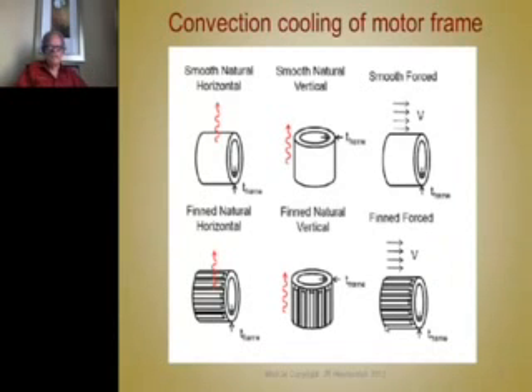The surface has something to do with it, whether the surface is finned or whether it's smooth. If it's finned, you're greatly increasing the surface area that's in contact with the air. That's obvious, and you can double, triple, quadruple the surface area just by putting fins on it. If the motor's mounted horizontal, natural convection is like this, or if the motor's mounted vertical, it's like this. Whereas if you have forced air, it doesn't matter how you mount it, because the air velocity is going to be blown from the shaft end across the thing.